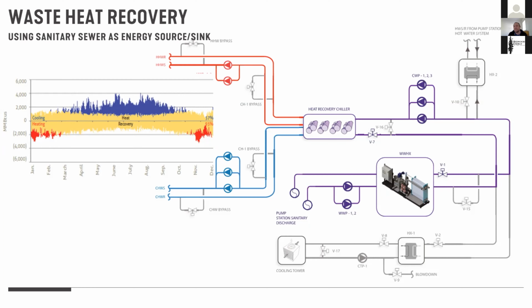We're using heat recovery chillers and a wastewater heat exchange to do all the space heating and cooling for this building. So in the summertime, that sewer water is cooler than outside air temperature. In the wintertime, that sewer water is warmer than outside air temperatures. So I get really high COPs year round.